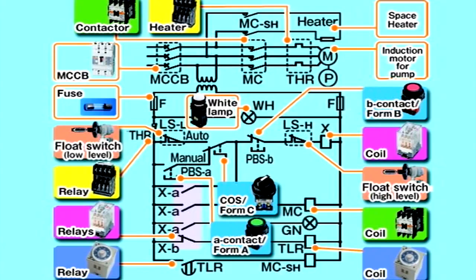This sequence circuit, controlling the level of the fuel oil settling tank within a set range, is comprised of various devices. Its high-level and low-level switches are B-contact types, allowing the relay to open when the float rises. Now let's take a step-by-step look at how the sequence circuit works.